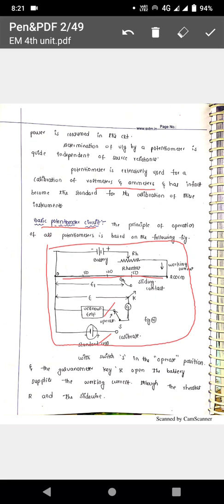When the switch is at position one, initially the standard cell is connected. By adjusting the working rheostat, a certain current flows through the slide wire. After measuring that current, the switch is placed to the unknown EMF position. When unknown EMF E1 equals E, the standard cell voltage equals the unknown voltage. By adjusting the slide wire to a position — say 50 or 100 cm — we obtain the null condition in the galvanometer. That is why it is known as a null type instrument.